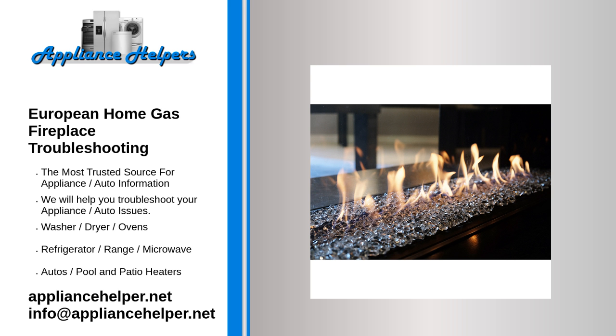The pilot flame under the hearth panel is not established. Remove glass and hearth panel, then check for proper pilot operation. If the pilot establishes with the panel off, then install panel and glass and adjust pilot flame high to low for best operation. Too much draft at pilot flame, poor flame impingement of primary thermocouple. Check venting installation. Use restrictor as required.